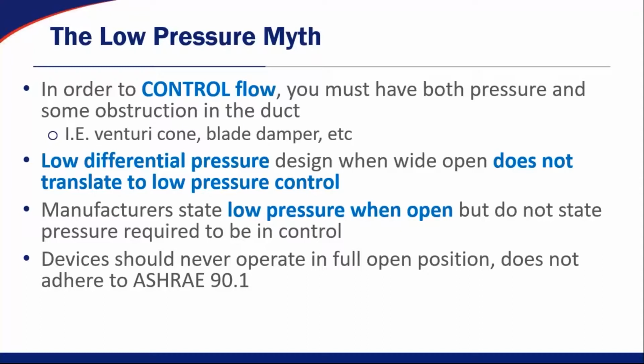Well, if you go back to ASHRAE 90.1 standards, which is trying to reduce your fan pressure to its minimum, get your brake horsepower, your fans, down to its minimum, ASHRAE 90.1 states that the devices cannot be 100% open. So if you're adhering to ASHRAE 90.1 to get your devices within that controllable range, they cannot be 100% open. Therefore, they will never run at the low pressures that are stated based on the ASHRAE 130 guidelines that they put in their ordering guides.